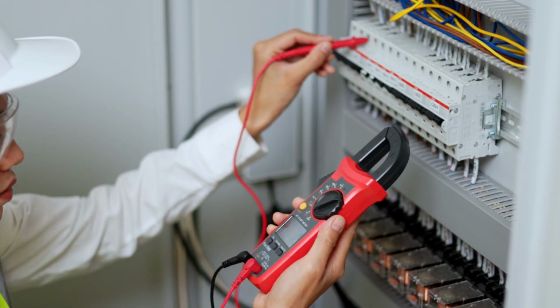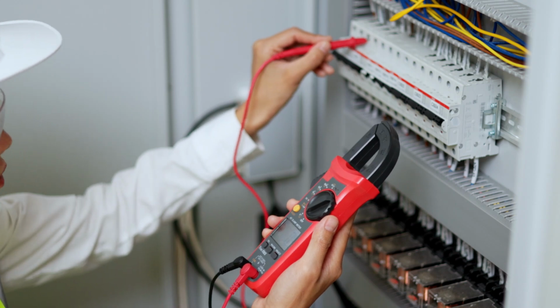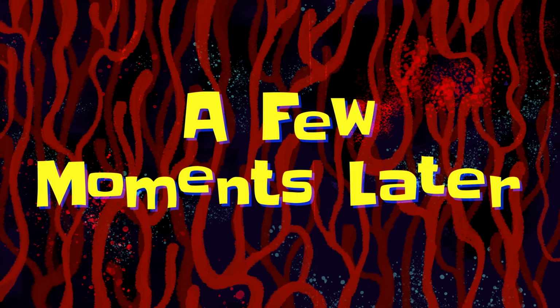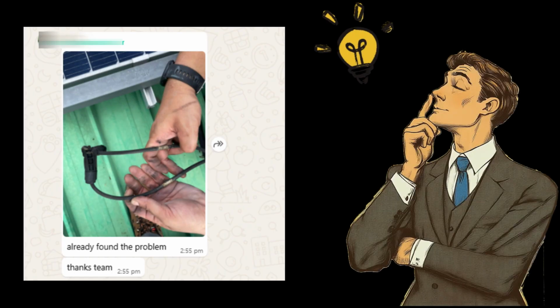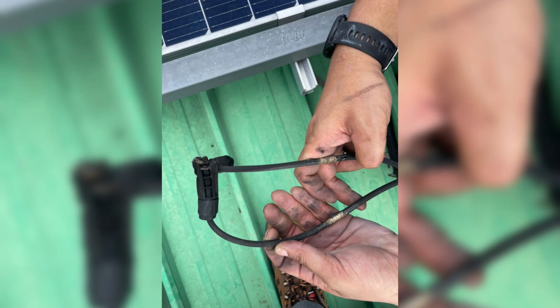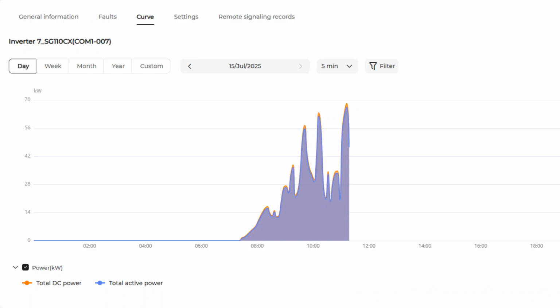We advised the installer to inspect and test all DC cabling. After a short while, they got back to us and confirmed the issue. A broken cable was found during the inspection. Once the broken cable was repaired, the inverter returned to normal operation.